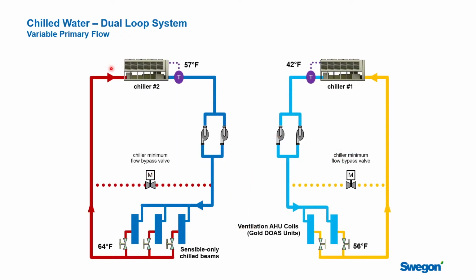Some other things that you see people do when we start talking about chilled beam design and chilled water plants to service that. One consideration would be to separate the loops, right? We have a system in here that would be servicing the chilled beams. We only need to make 57-degree water. If we could set up a separate loop for that, it would have a significant impact on these chillers. You could pick up 25 or 30% of the efficiency on the chillers just because in the dead of summer you would only be making 57-degree water instead of 44. So a huge improvement on that.